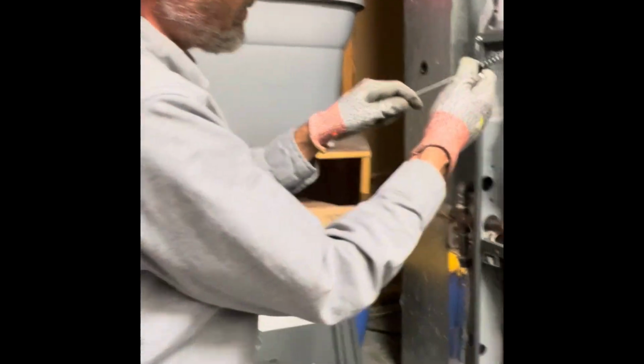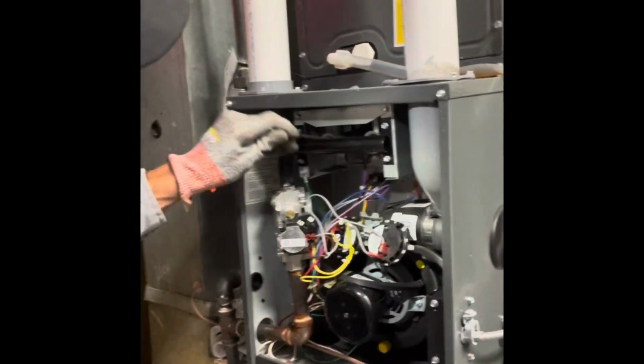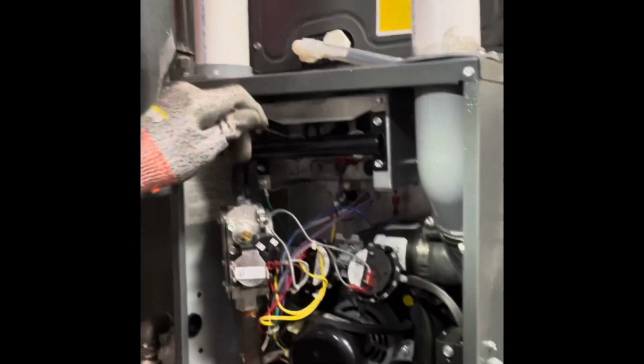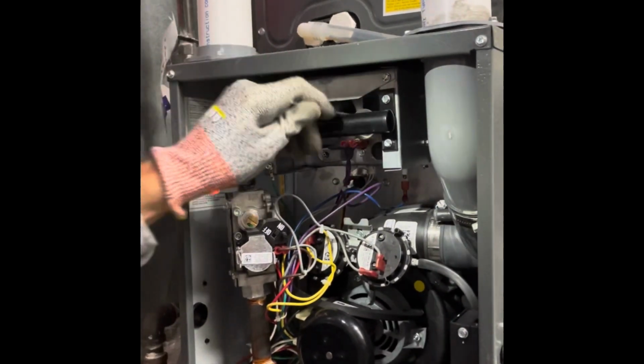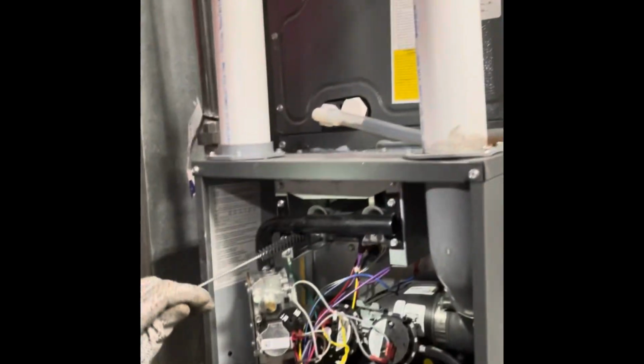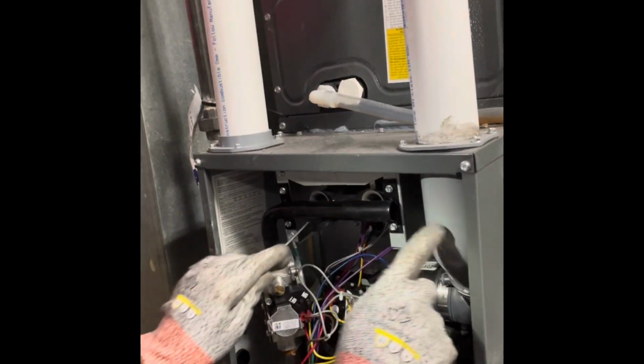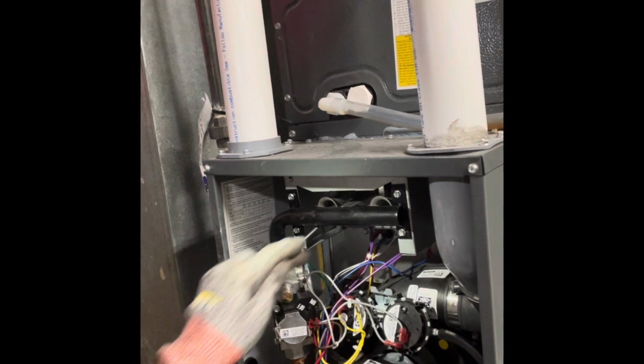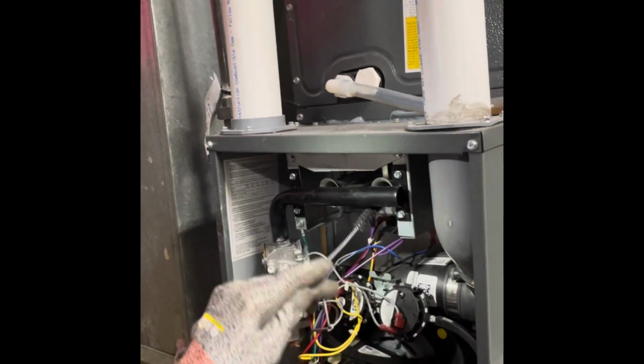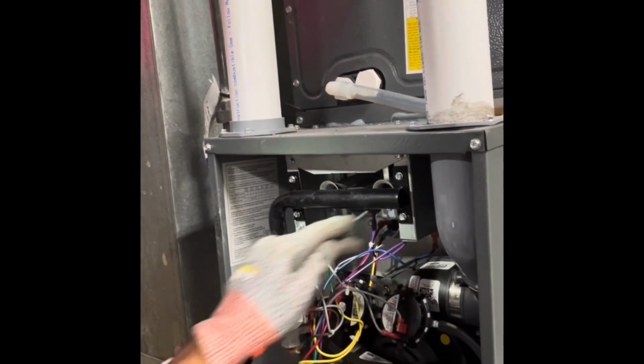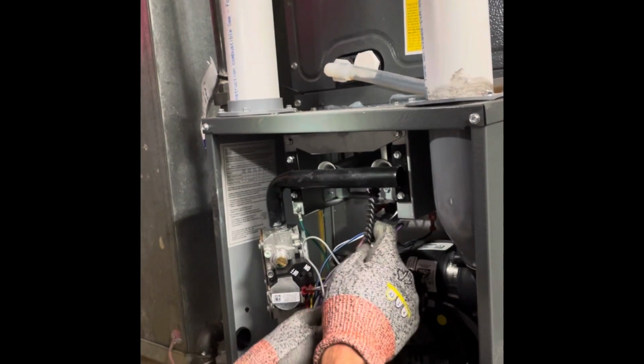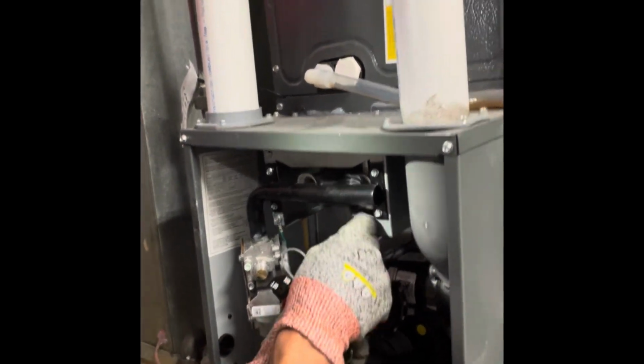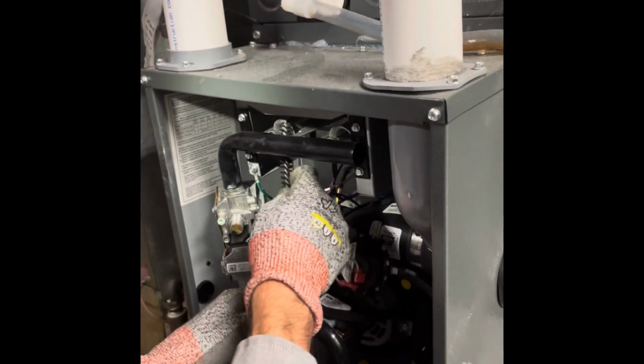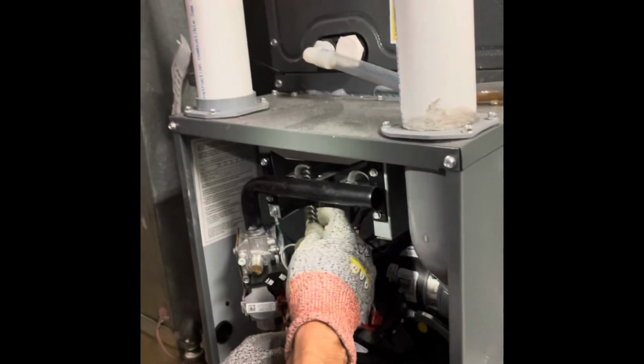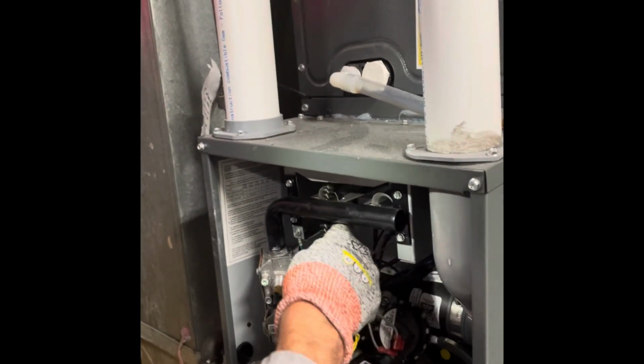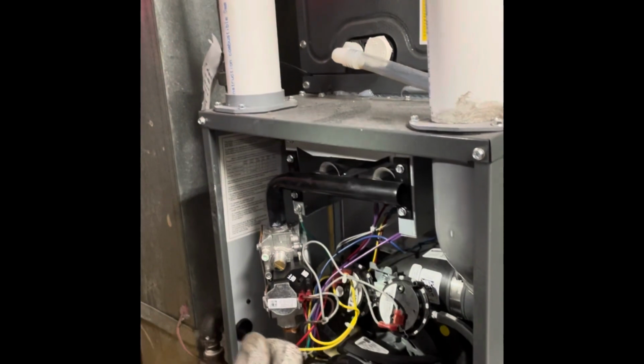Right at the very top, we're going to take a burner brush to the burners. We want to scrub off the carbon buildup, because if we get too much carbon building up in here, we could have a high CO reading in the exhaust. So we just scrub that up like that. I also like to go across the orifice part here, just in case we get spider webs. Spider webs are notorious for making high CO.